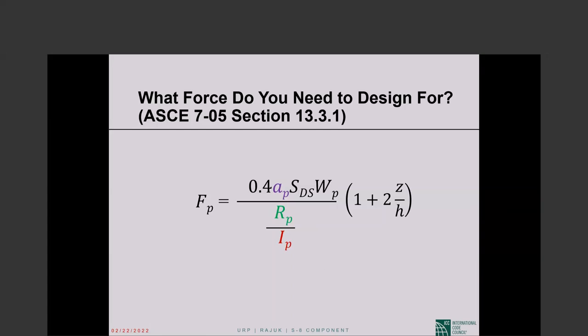So we are talking about the peak ground acceleration multiplied by a dynamic amplification factor, A sub P, times the weight of the component, W sub P, divided by R sub P, the component response modification factor, and then I sub P is the importance factor. Basically it's 0.4 S sub ds times W sub P, the peak ground acceleration multiplied by the weight of the equipment.